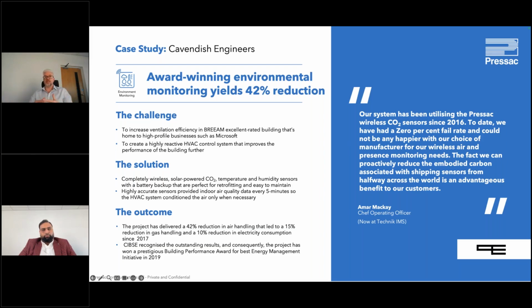So that the AHUs only triggered or activated when CO2 exceeded a particular threshold. This reduced the amount of time they were operating, extending their lifetime and maintenance intervals, but also reduced energy massively, because you're not doing air exchanges and heating and cooling air and pushing it into a space if you don't need to.